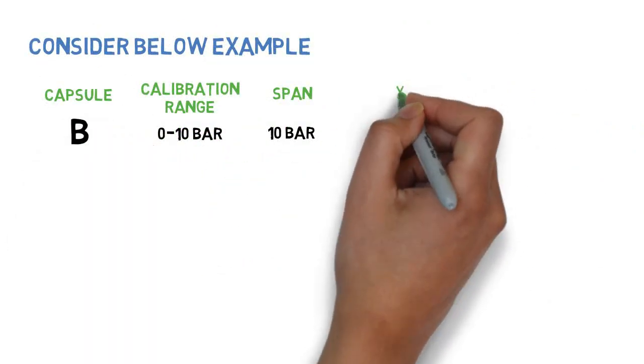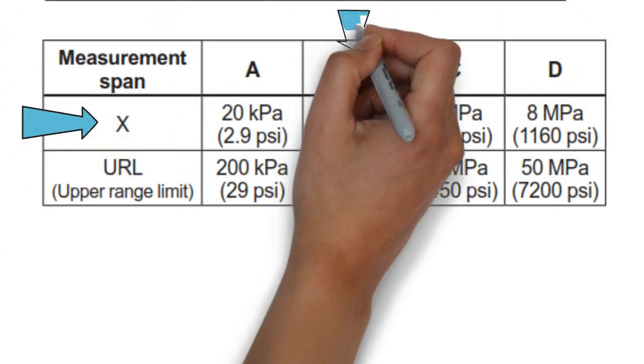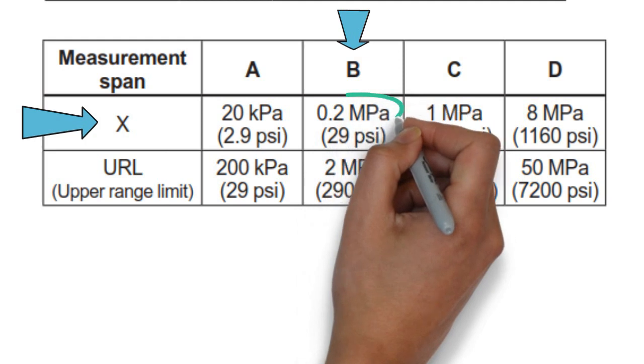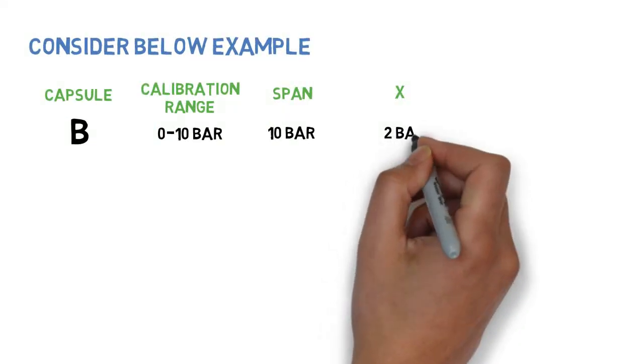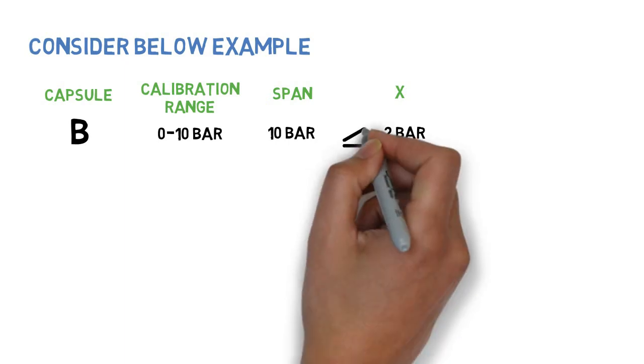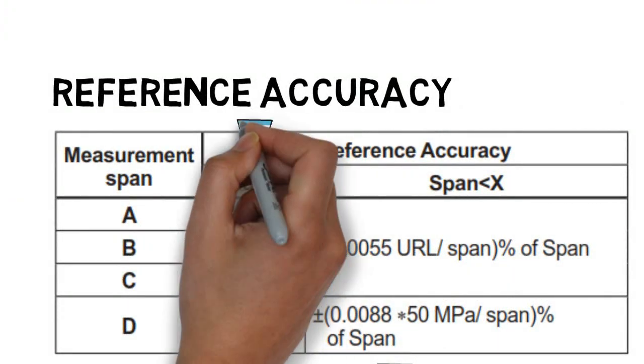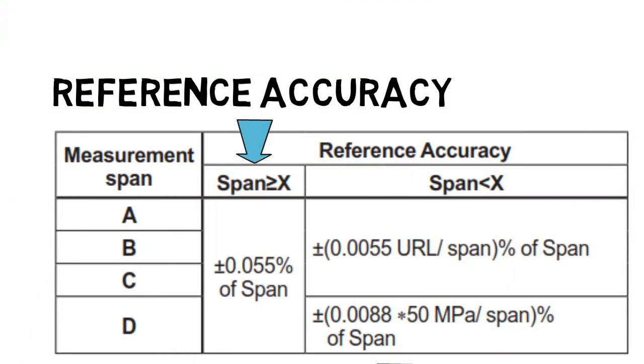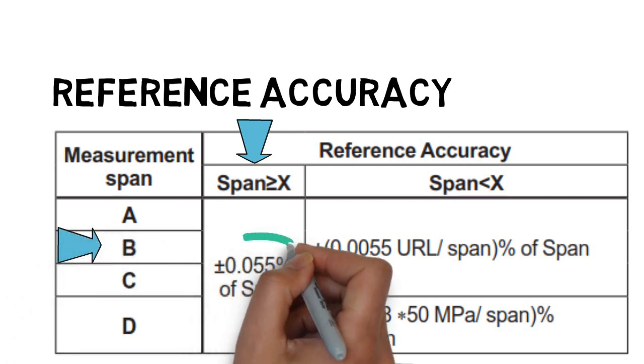X: Value of X for capsule B is 0.2 MPa or 2 bar. Span 10 bar is greater than X 2 bar. When span is greater than X, accuracy for capsule B shall be 0.055% of span.